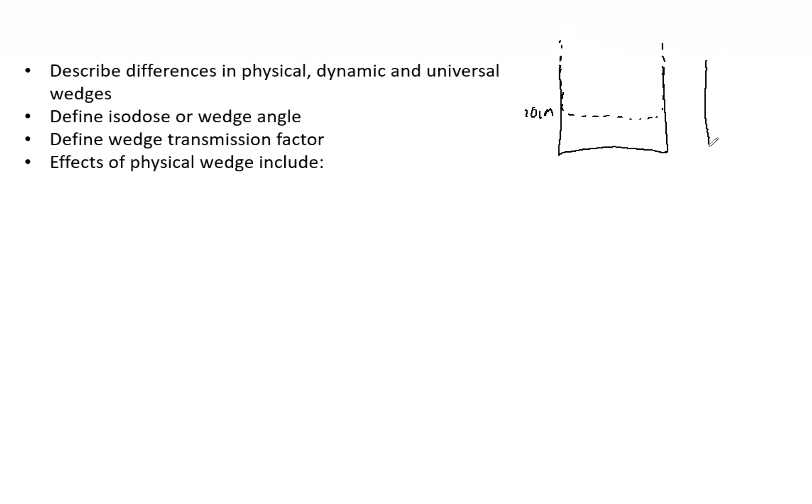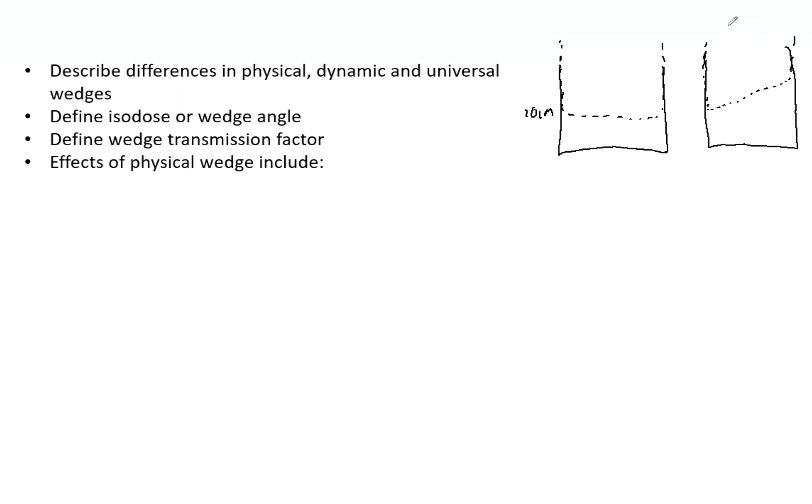If you have the same water phantom with a wedge, you may have isodose lines that come down and then have this curve to them. This curve, this angle right here—say that's 45—that's when your wedge angle is 45 degrees. So it's not the actual physical angle of the wedge, rather how much of an angle the isodose lines curve at that specified depth.